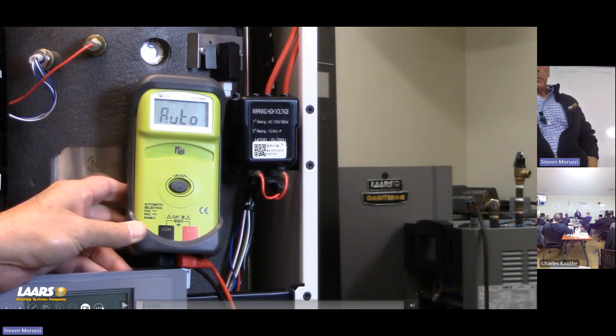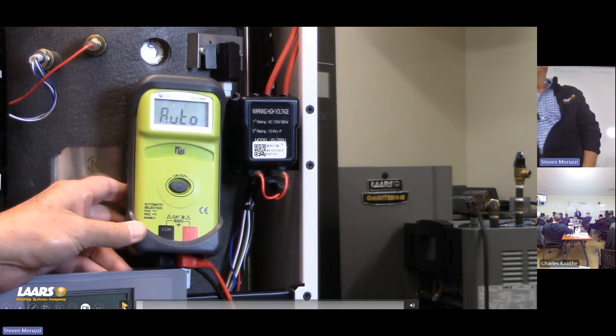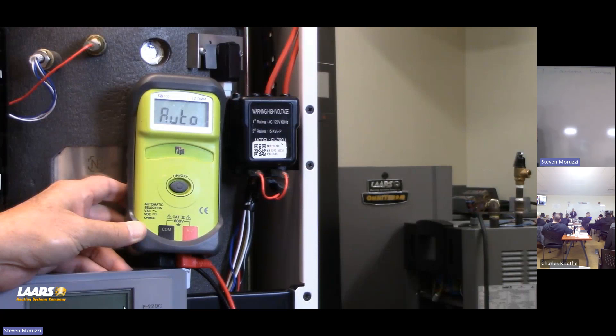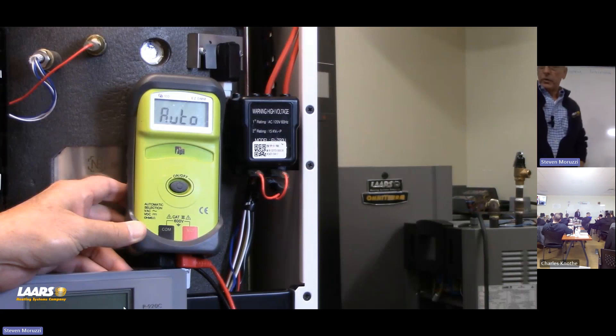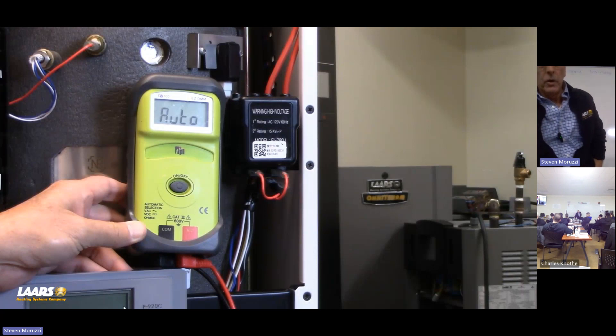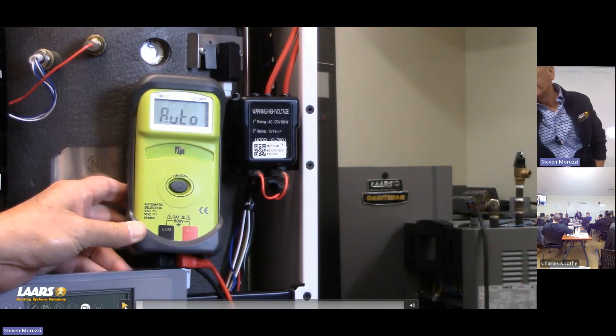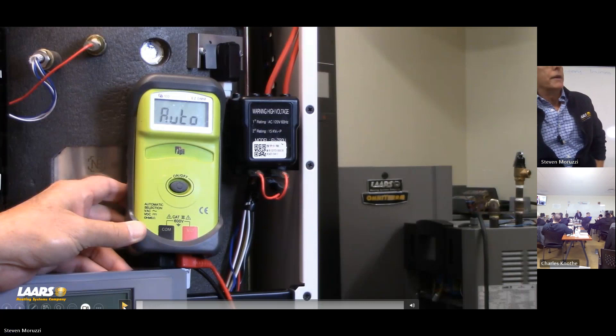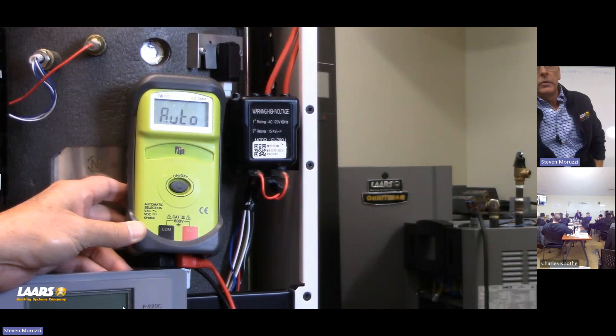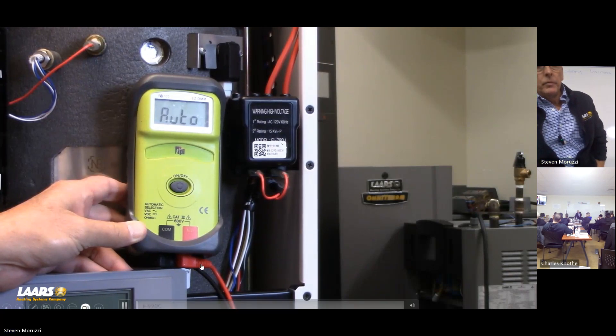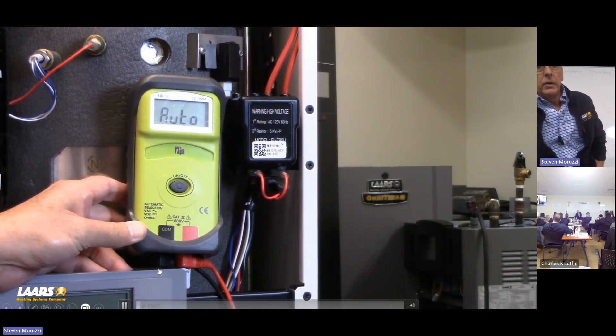That's why we bring it up. We get I don't know how many calls come back to the manufacturer saying it's the manufacturer's fault, and they want components for free and covered under warranty. No. National Fuel Code will tell you half-inch pressure drop. Now that's when you've got to get in, look at your regulators, your gas line sizing. All of our manuals do give you a distance for three-quarter inch, one inch.